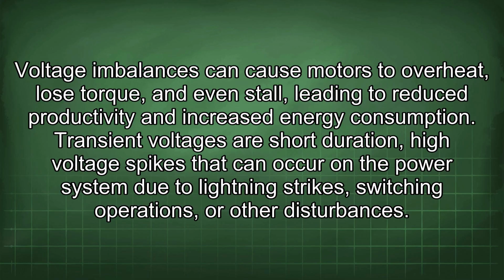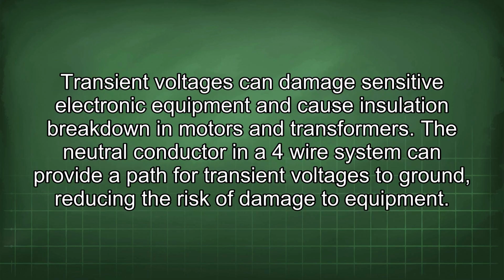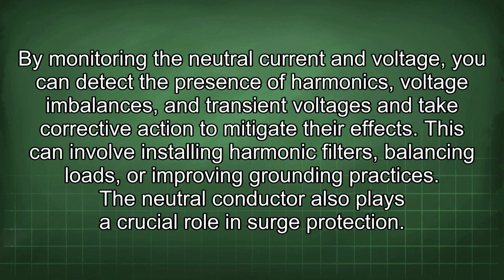Transient voltages are short-duration, high-voltage spikes that can occur on the power system due to lightning strikes, switching operations, or other disturbances. Transient voltages can damage sensitive electronic equipment and cause insulation breakdown in motors and transformers. A neutral conductor in a 4-wire system can provide a path for transient voltages to ground, reducing the risk of damage to equipment. By monitoring the neutral current and voltage, you can detect the presence of harmonics, voltage imbalances, and transient voltages and take corrective action to mitigate their effects. This can involve installing harmonic filters, balancing loads, or improving grounding practices.